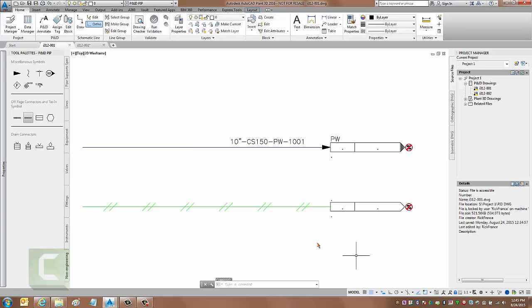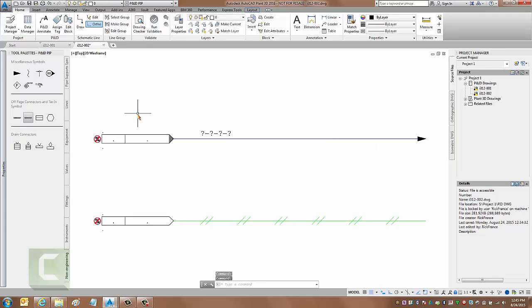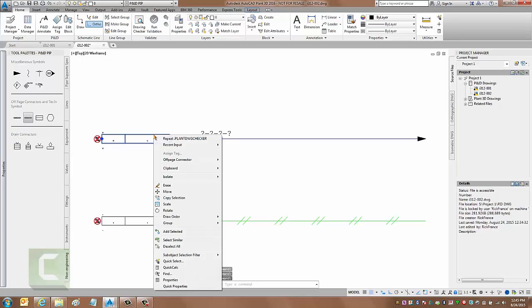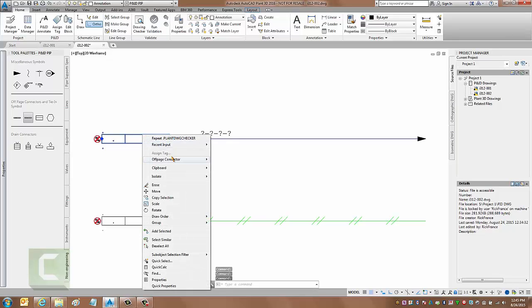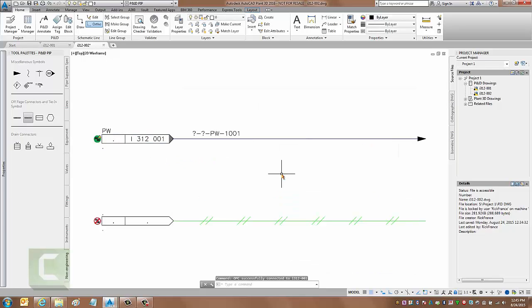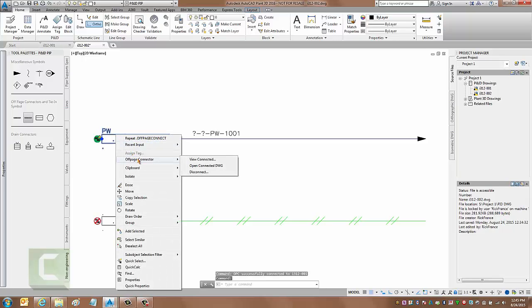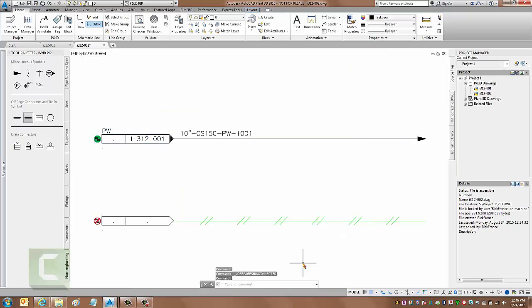So you always have to work from a line that has a line number. If I look here on the second sheet, select this one, connect up to a connector on the first sheet, you can see it sees that connector. I can easily just connect it right up and it carried over the information for that pipeline. Of course I still have to go into the view connected and connect the line segments to get the rest of the line number over. But it was easy to connect, I just always have to remember to come from a predefined line when I'm connecting these up.